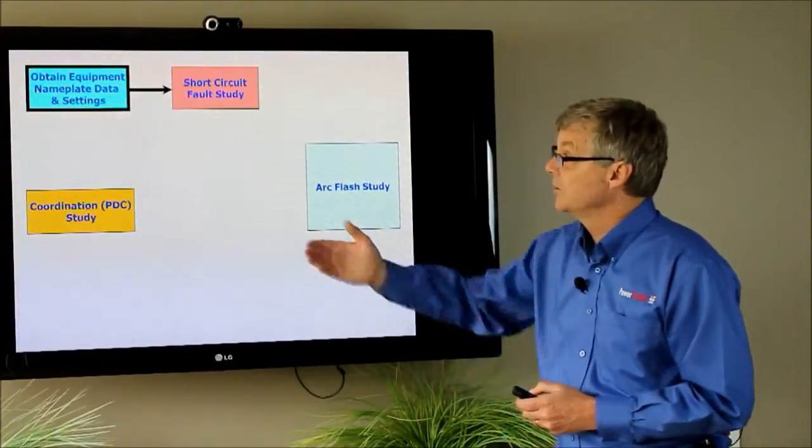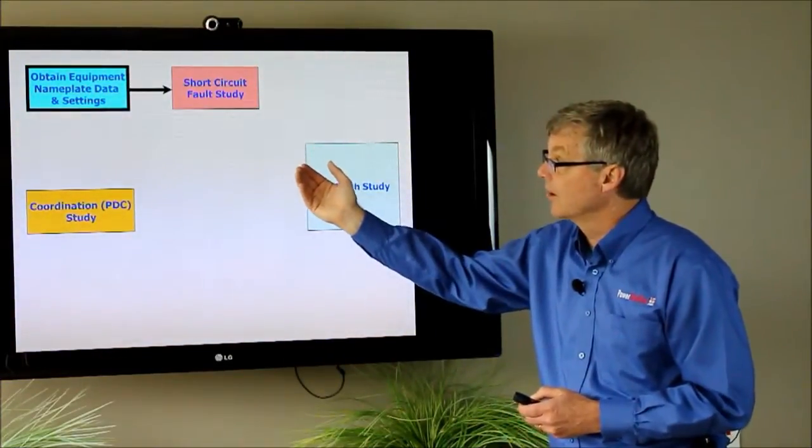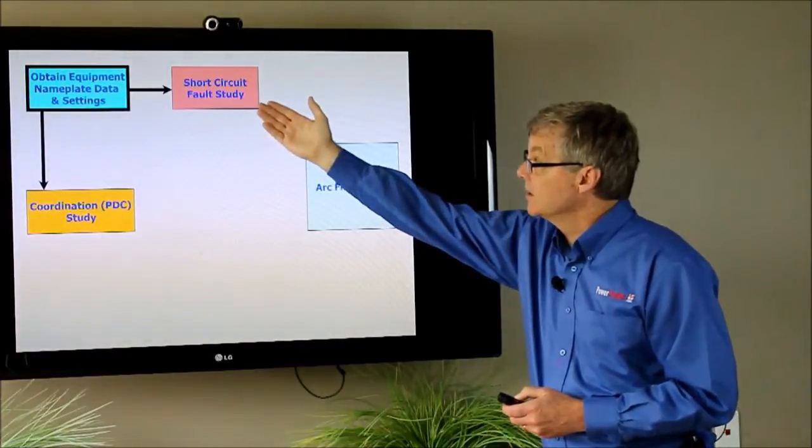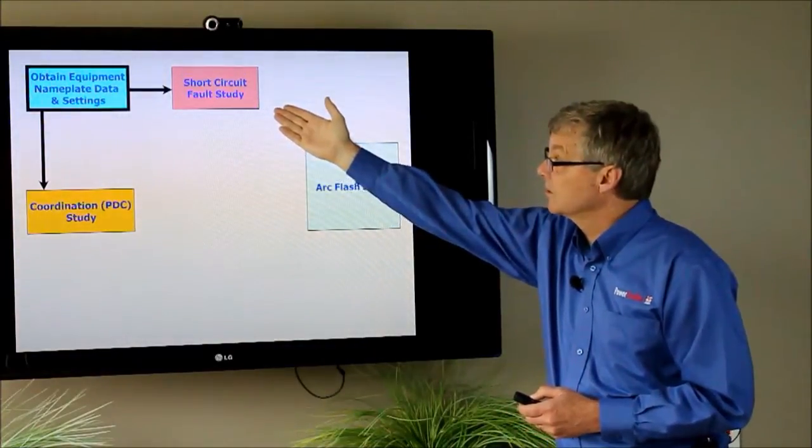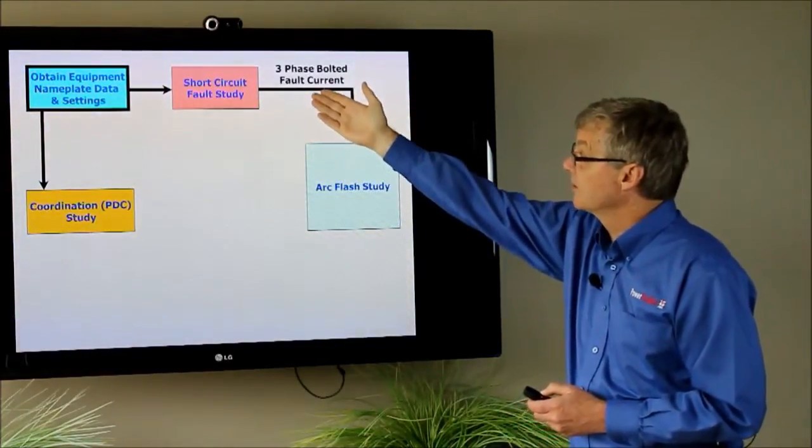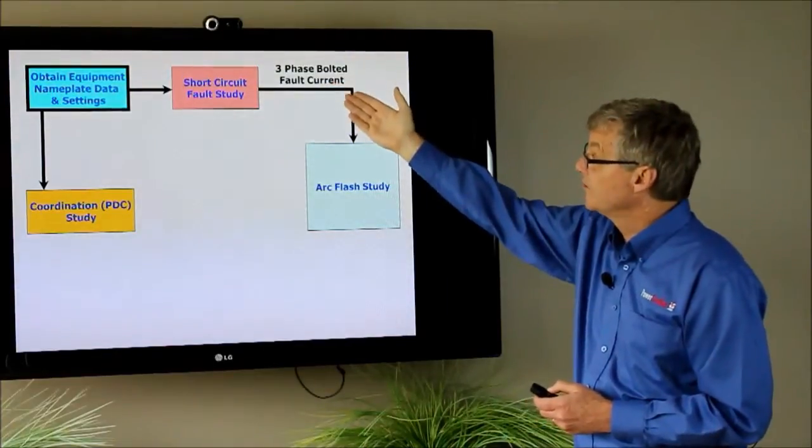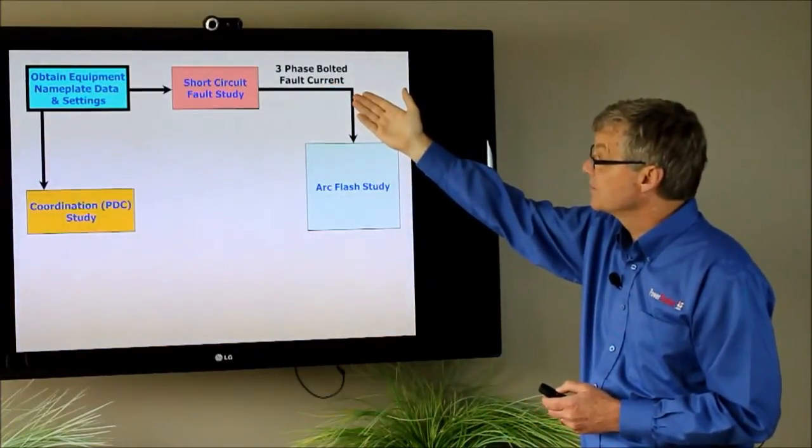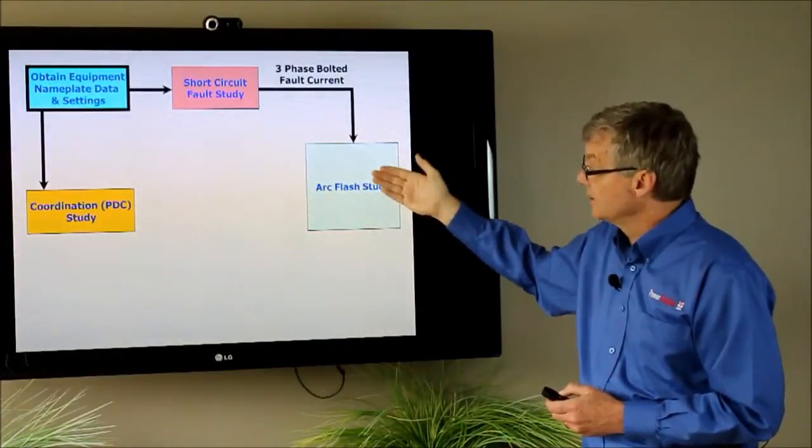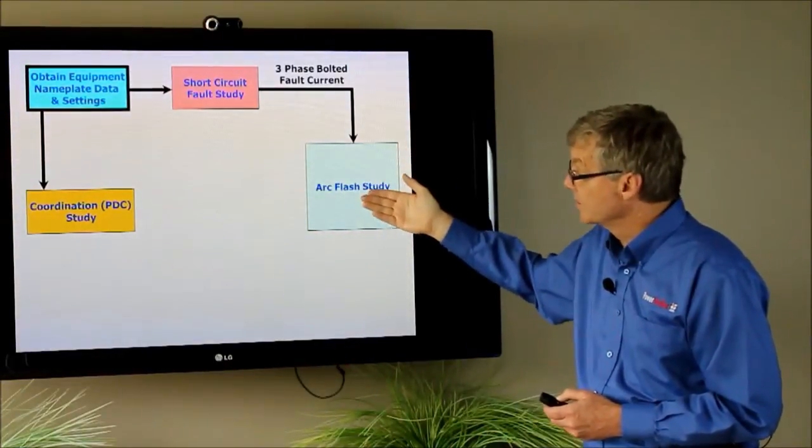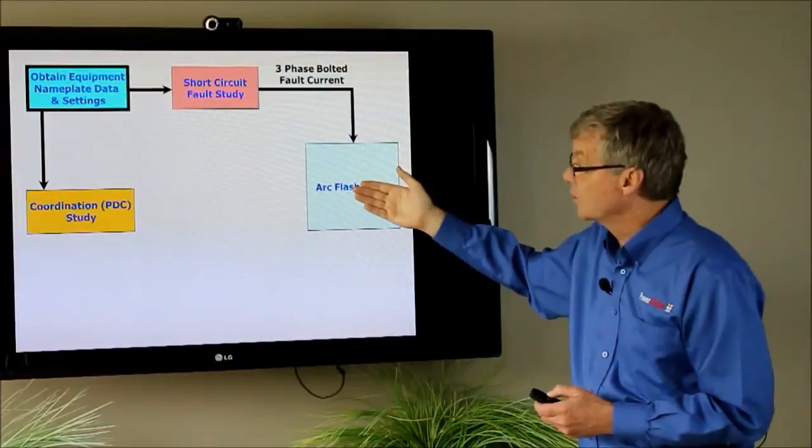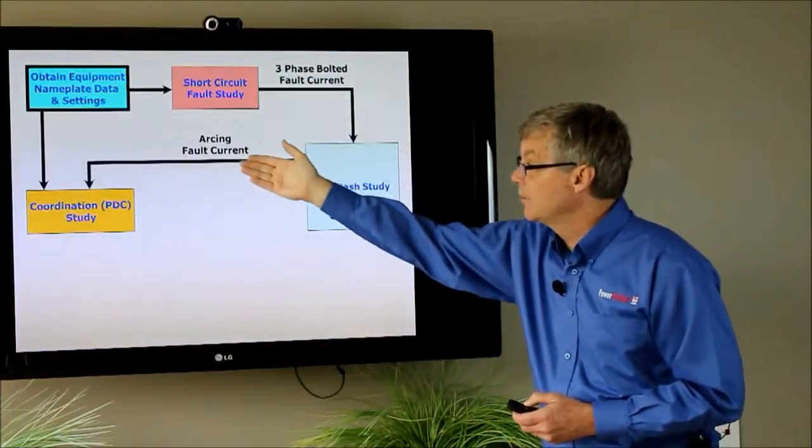Once we have that information then we input that into our computer program and the computer program will do a short circuit calculation. It'll figure out what the three-phase bolted fault currents are and this goes into the arc flash module and depending on some other parameters like voltage and type of equipment it will output what's called the arcing fault current.